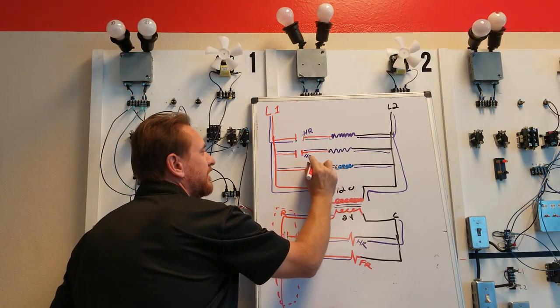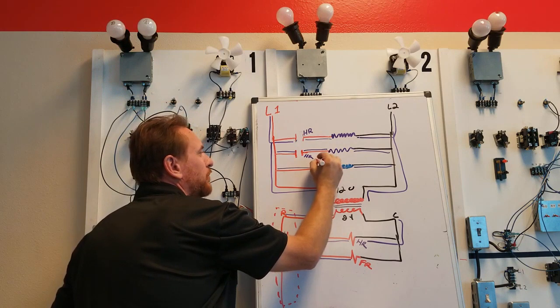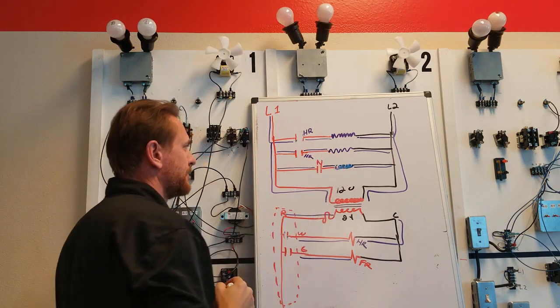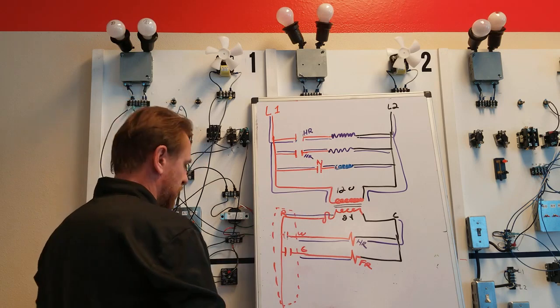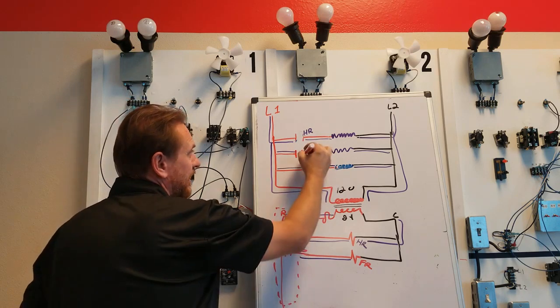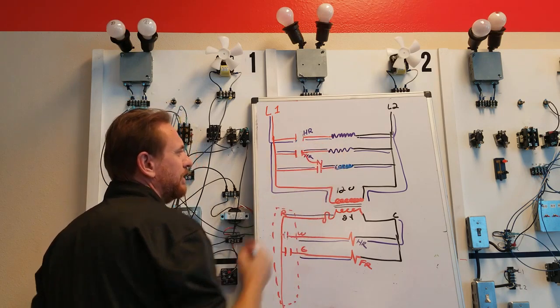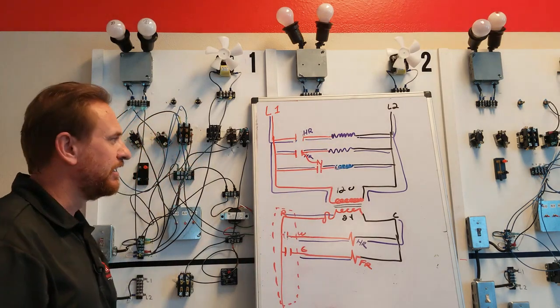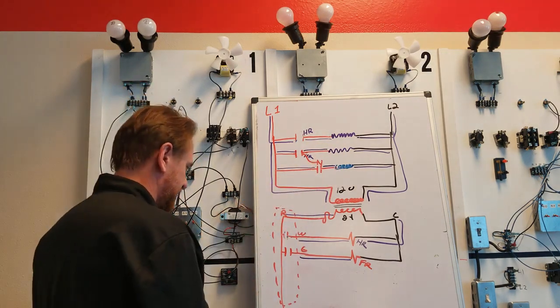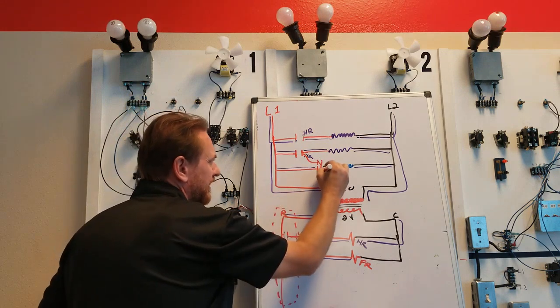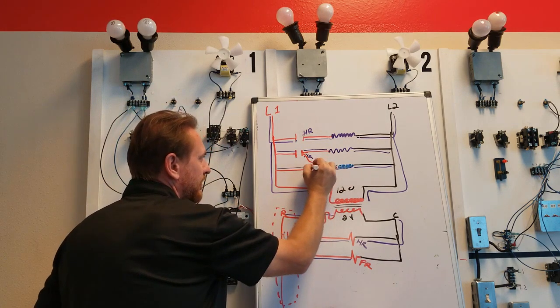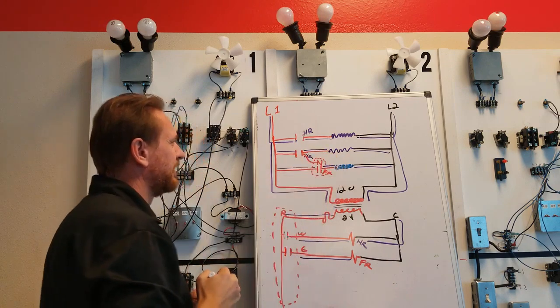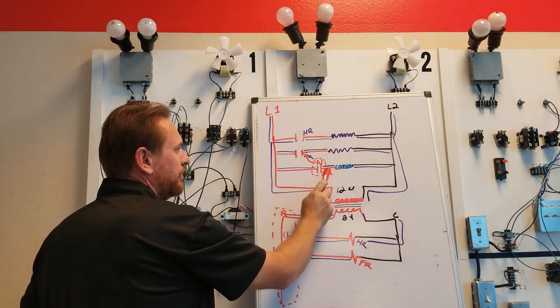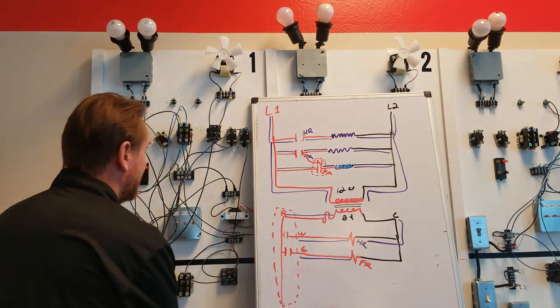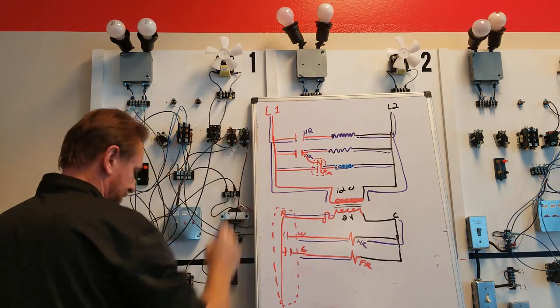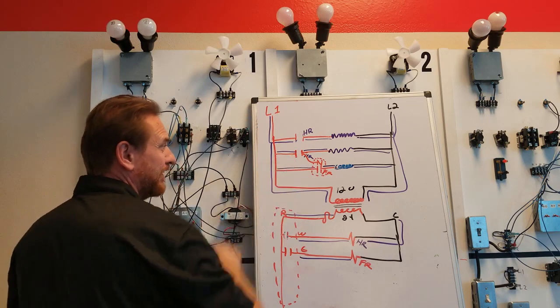So what we're going to do is have this wire come up to a normally closed connection. And we're going to connect one wire from the output of this heat sequencer to the input of the normally closed connection. So in this component right here, that we need to label FR for fan relay, this is all one component. If I look, I should have 3 wires. 1, 2, and 3 wires come into this. If I look up here, I only have 2 wires. So I'll need to add this one wire that's not highlighted.